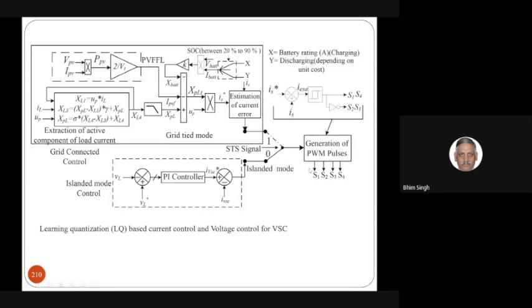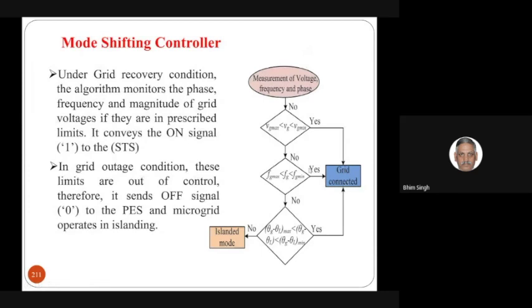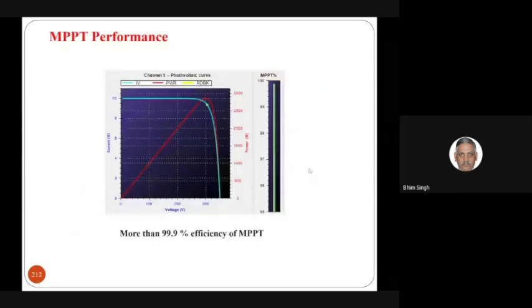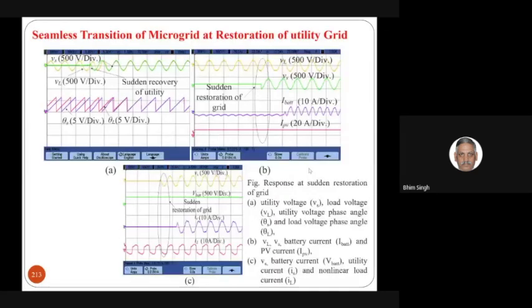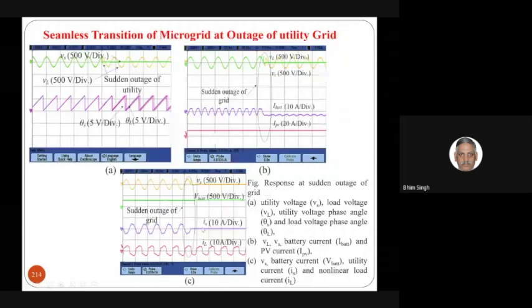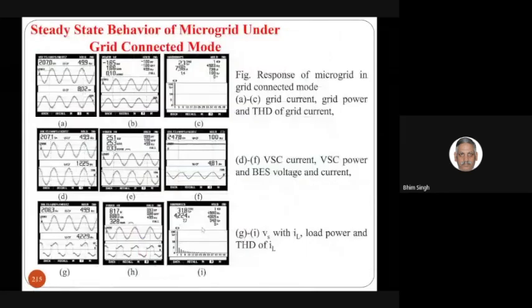Also, how the mode shifting controller with synchronization and islanding takes place with the MPPT remaining because the battery is there. So here the grid appears, and you can see how the inverter angle shifts towards the grid. When the grid appears here, we are able to close the switch here, and grid current starts coming, typically like here, after 3 cycles. But the load is not affected. Load voltage is also not affected, and how it is when islanding takes place.